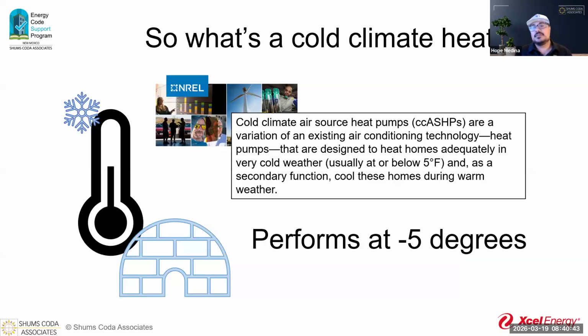If you've done mechanical systems before, for instance looking at a Manual J, you know there's a temperature differential every gas-fired furnace is designed for, where the outside air coming in needs to be heated to run through the heat exchanger. Once it gets really, really cold, there's the same thing: a curve and a drop-off where efficiency is harmed. Now, it'll still operate.